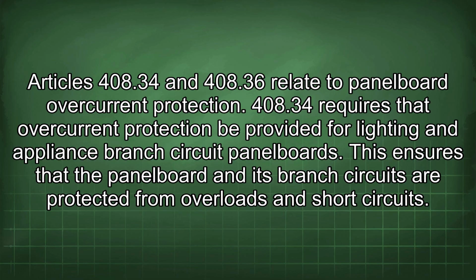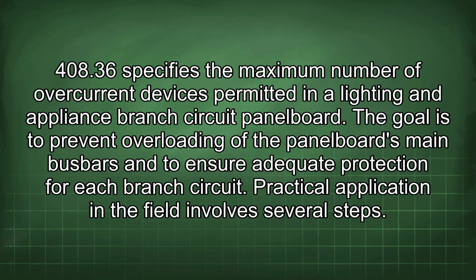Articles 408.34 and 408.36 relate to panel board overcurrent protection. 408.34 requires that overcurrent protection be provided for lighting and appliance branch circuit panel boards. This ensures that the panel board and its branch circuits are protected from overloads and short circuits. 408.36 specifies the maximum number of overcurrent devices permitted in a lighting and appliance branch circuit panel board. The goal is to prevent overloading of the panel board's main bus and to ensure adequate protection for each branch circuit. Practical application in the field involves several steps.